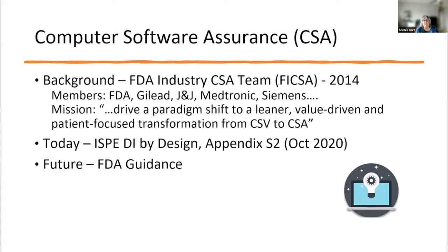How often is a backup and restore tested? I've had instances where the validation went great. The backup was validated and everything, but after the validation, the backup actually never occurred on the instrument. So it was never being verified that it was happening. And restores do need to be tested.